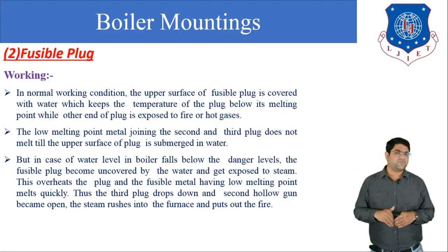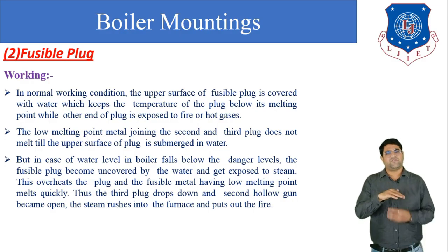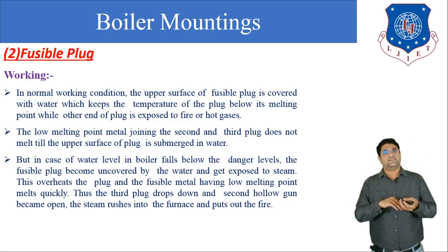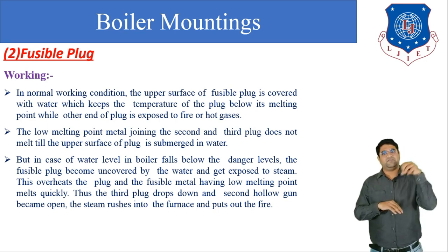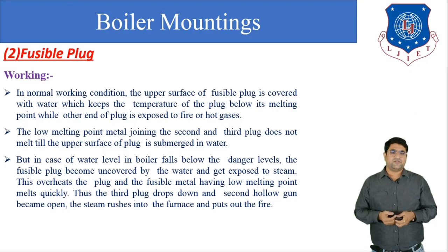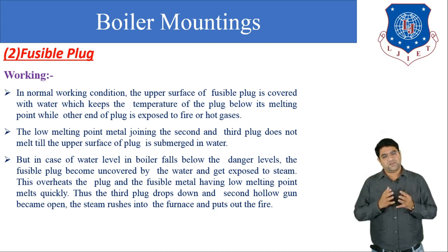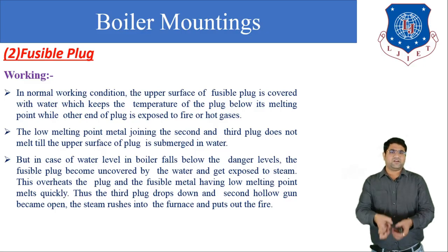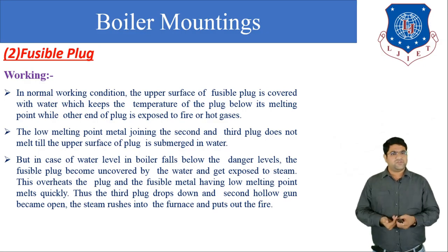So when it is submerged in the water, it will continuously transfer the heat from the firebox to the upper surface. Now, above there is water, so when the fusible plug is submerged in the water, it will take all the heat which reaches the fusible plug. But in the case the water level falls below the danger level, then what happens? The fusible plug becomes uncovered by the water and gets exposed to the steam, and we know that steam is a bad conductor of heat. So it will not take all the heat which reaches the fusible plug.